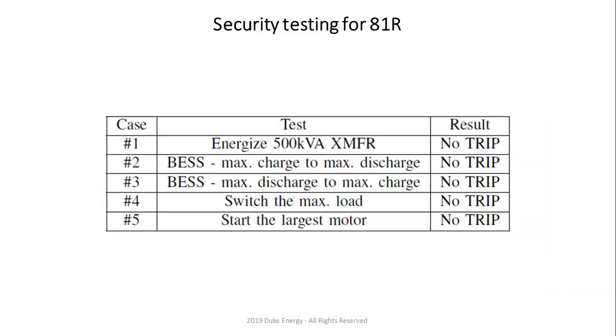What you have to do is account for security, right? You have to see what happens when the majority of things change within the microgrid, and do this transient analysis so that you don't trip when you're not supposed to trip. So we have done these 5 cases, which are 5 critical cases in our study, just to make sure that we don't trip on the 81R setting, right? And you can clearly see that for none of these cases we trip. So remember, every time you do something, you have to do the fault analysis or reliability analysis, but you also have to do security analysis, right?